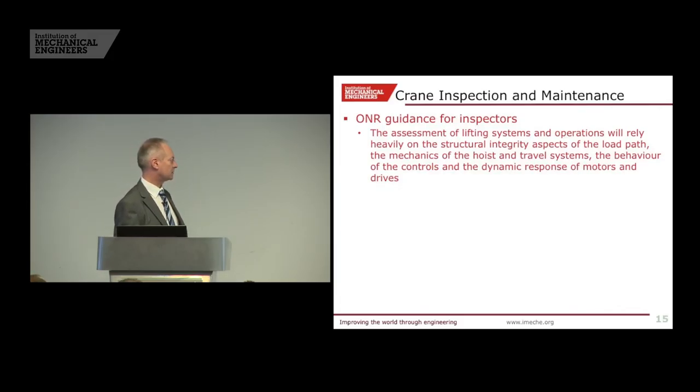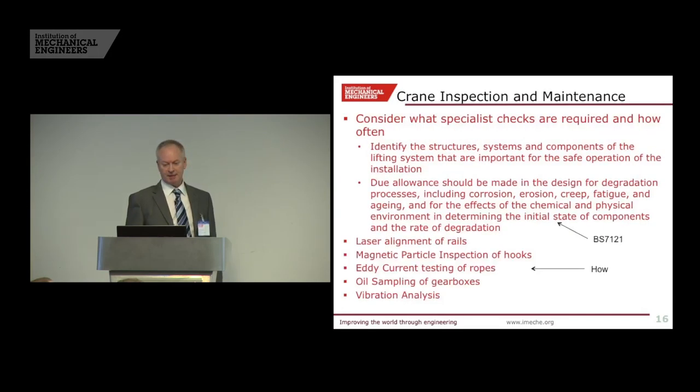What do ONR inspectors look for? We've had some insights on that — they're looking at the load path, that's basically where the main focus is. Specialist checks on structures, design for degradation processes including corrosion, erosion, chemical and physical environment — obviously we're near the sea at Doonray; most of the facilities are inside, some are not. What tools can you use for inspection? Laser alignment of rails, magnetic particle inspection of hooks, eddy current testing of ropes, oil sampling of gearbox and vibration analysis. This is a forward bit of thinking — it gives us some leading indicators. There are references to British Standard 7121 about what you should look for.